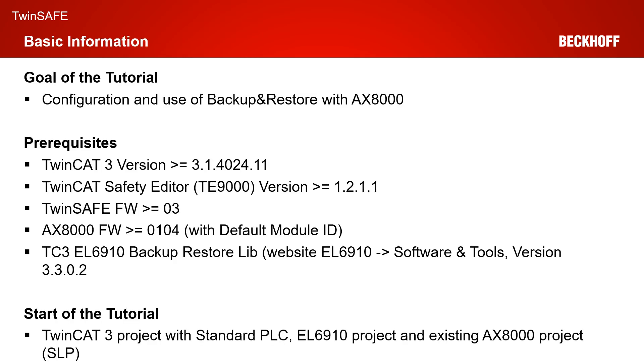The goal of today's tutorial is to configure and use the backup and restore mode with the AX8000. We have an EL6910 and an AX8000 and both have a safety project. We want to configure the backup and restore mode so that we can change the EL6910 and/or the AX8000, and the safety project is restored by our backup and restore mode without anybody using TwinCAT 3.